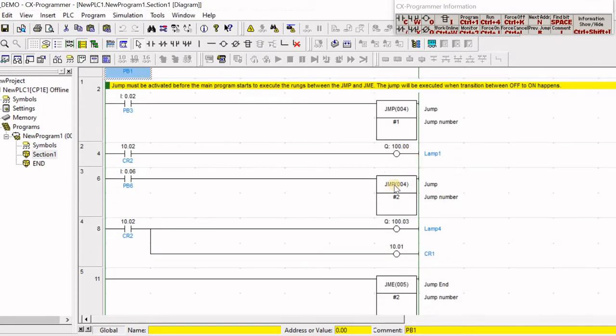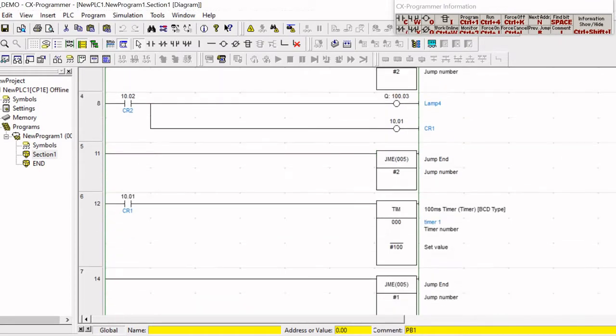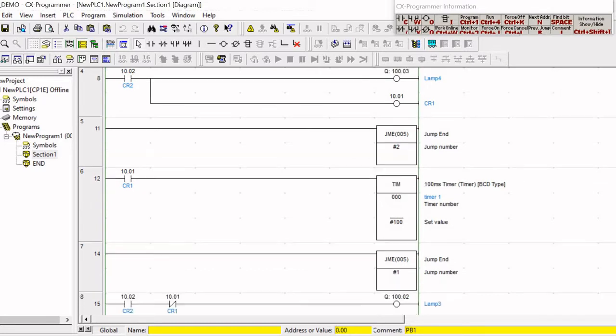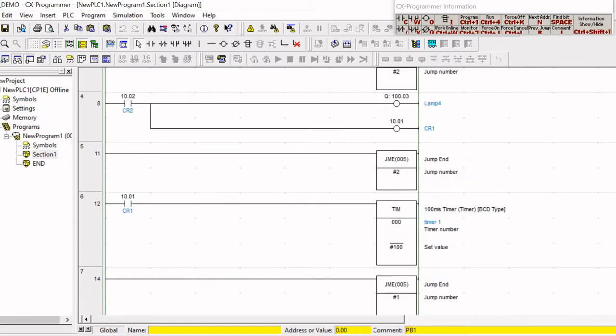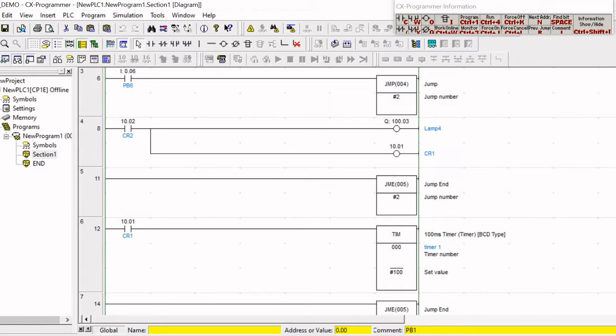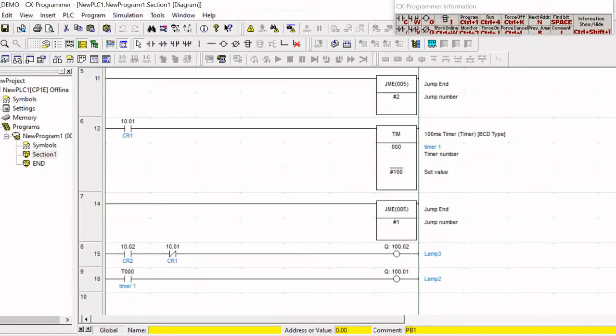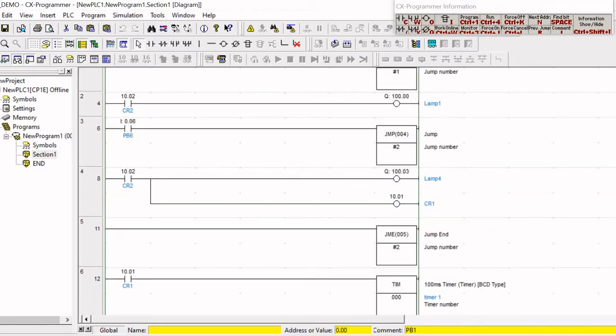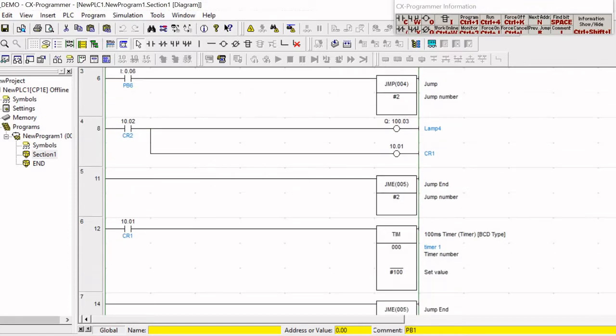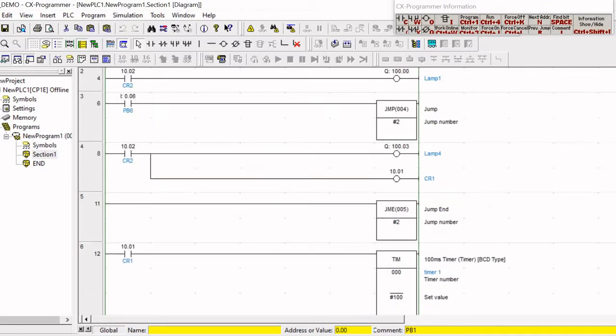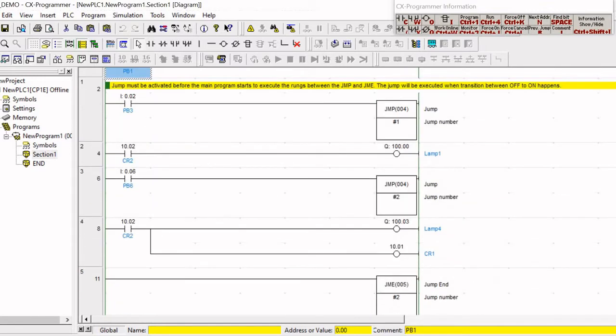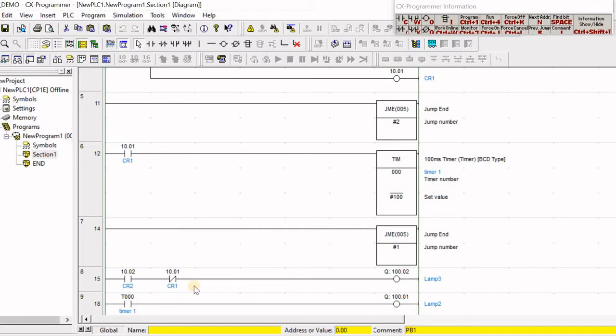If I take jump number two, that means I'll be executing lamp number one and the timer, because CR1 is not going to work since we jumped the second one. Also lamp three and two. If we run everything, every line works except rung number eight. Rung number eight is not working because we have CR1 normally closed, so it breaks straight away when CR1 is activated.